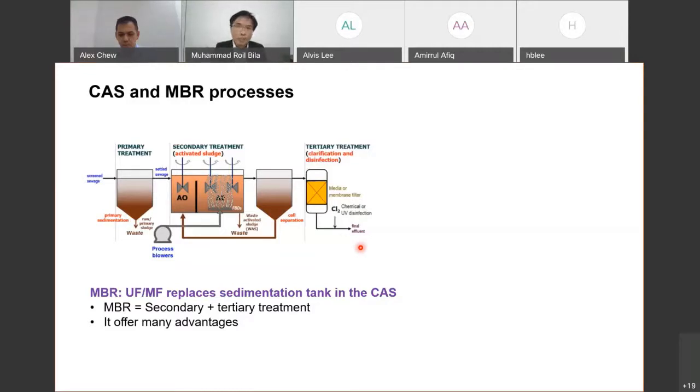What MBR does is basically employ ultrafiltration or microfiltration to replace the sedimentation tank. And when we replace the sedimentation tank with membrane filtration, we get the whole of this. Instead of getting only secondary treatment, we will also have an effluent quality that meets the combination of secondary and tertiary treatments. And there are many advantages that I will discuss later on.